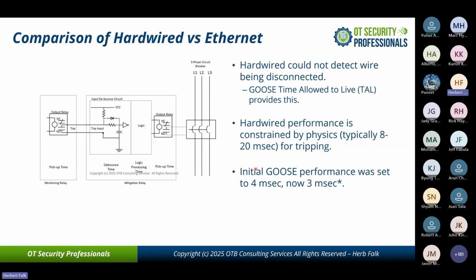So the question is, could Ethernet multicast beat the 8 to 20 milliseconds and be in the 4 to 3 millisecond range? Now, that means from the time the monitoring relay or this device decides that it needs to send a message to the time this device receives the message. And we all know Ethernet is very fast, but that's what the 4 or 3 milliseconds means, just so you know.